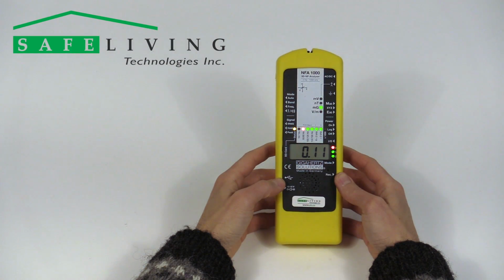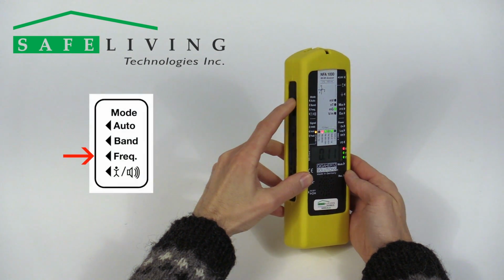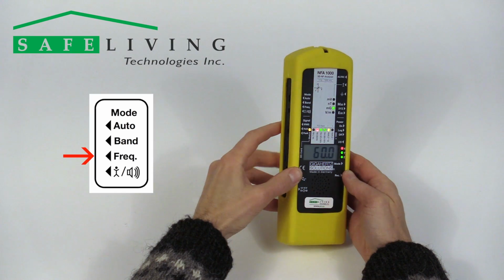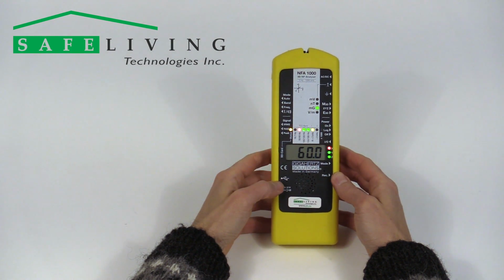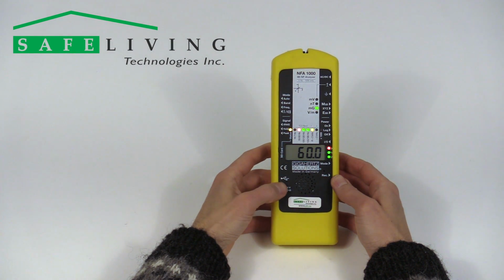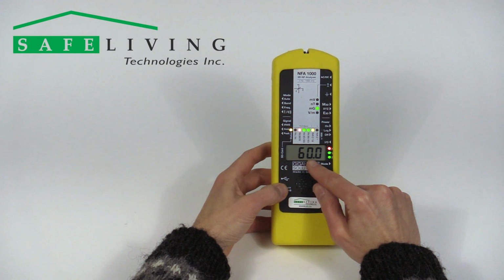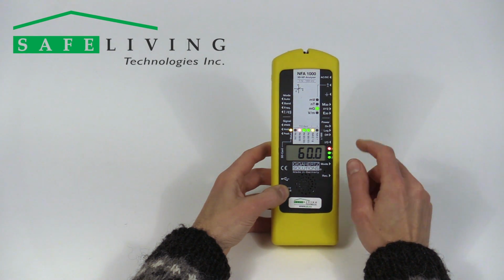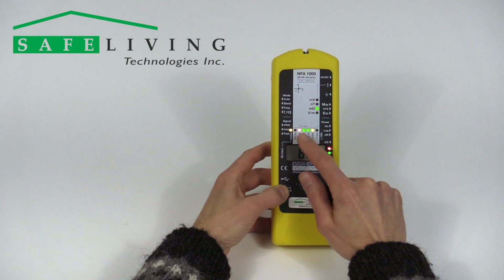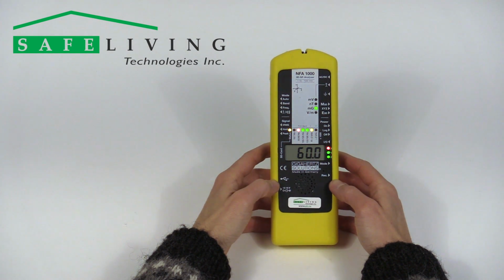If you would like to know the exact frequency of the highest measured level or dominant frequency, then change the mode switch to frequency as shown. The dominant signal must be at a significant level to use this functionality. The LCD display will then show the frequency in hertz of the strongest signal up to 30 kHz or 50 kHz with increased tolerance. Again, the LED of the corresponding band will be red. The meter is now what's referred to as a frequency counter.